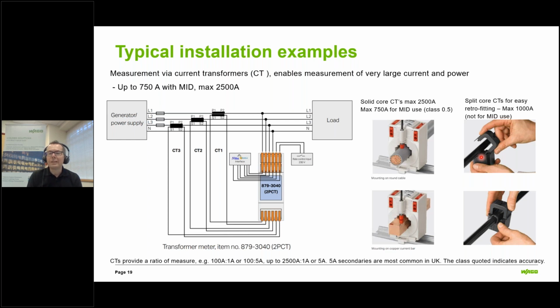One point to consider, though, is that the CT is positioned around the individual conductor. So if it was a three-phase cable, which is typically three phases and an earth, not always a neutral if it's a motor, with external insulation around all three cables, then of course you can't individually select the correct phase for the CT. So that needs to be considered. But if they're accessible as individual phase conductors, then in principle they can be snapped over the cable without disturbing it. But I would encourage people to check with safe systems of work processes.